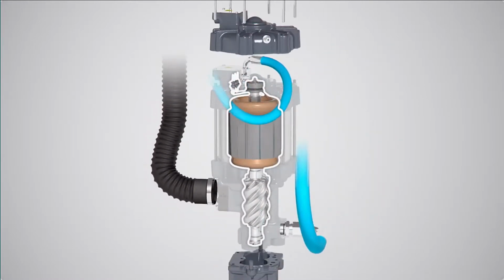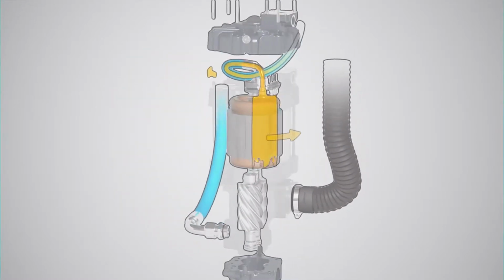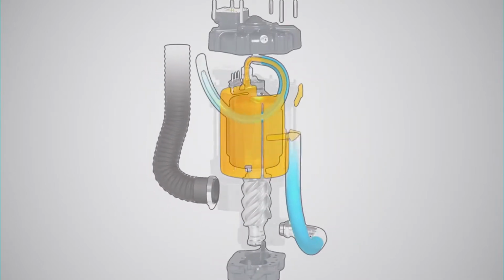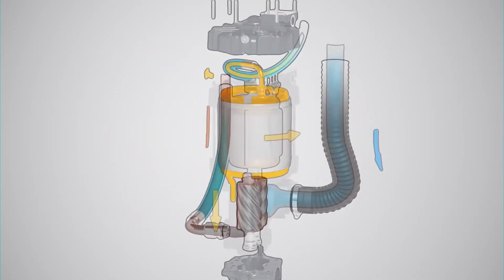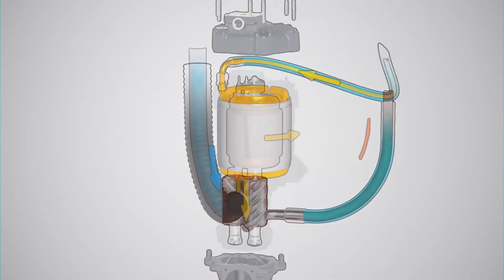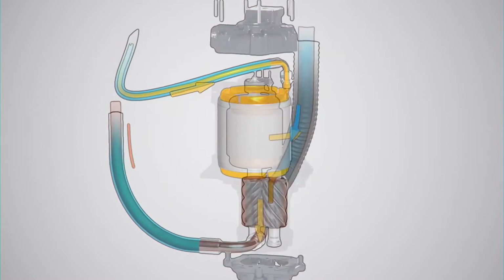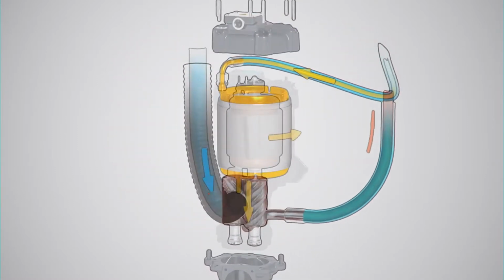Channels in the top cover ensure proper lubrication and deep cooling of the motor bearings, making them maintenance-free. The motor cooling is independent of the motor speed, ensuring optimal cooling in any working condition, also at low motor speeds. Overall, lower temperatures result in a longer lifetime of our motor and increased uptime.